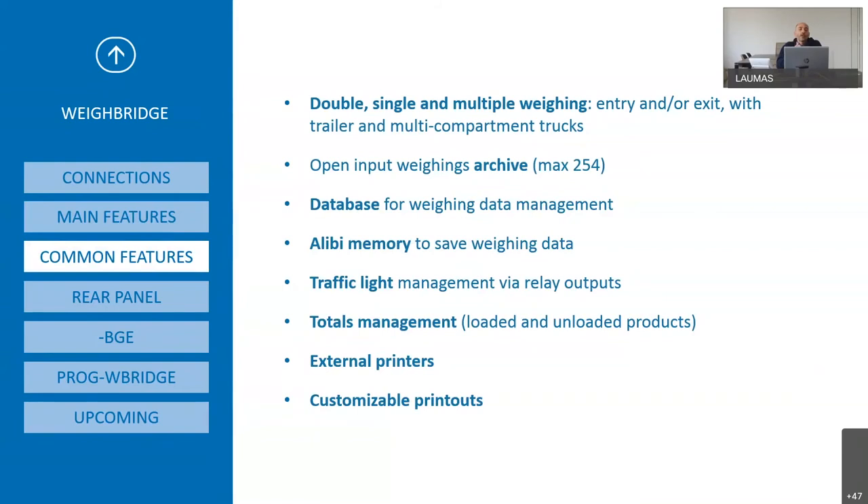The Weighbridge software manages double, single and multiple weighing — entry or exit — with trailers and multi-compartment trucks. It can have up to 254 open inputs, a database for weighing data management, and alibi memory to save weighing data in case the system is homologated — in Italy it is almost always homologated. You can manage traffic lights via relay outputs and total management of loaded and unloaded products.